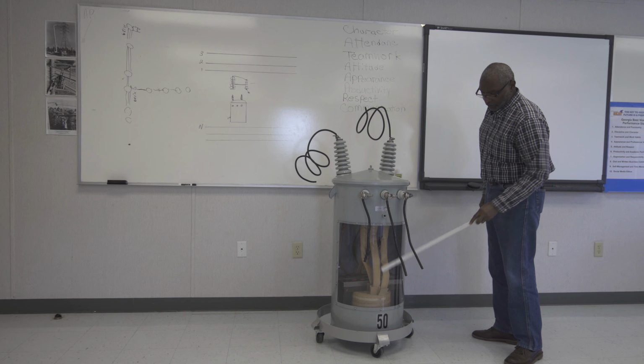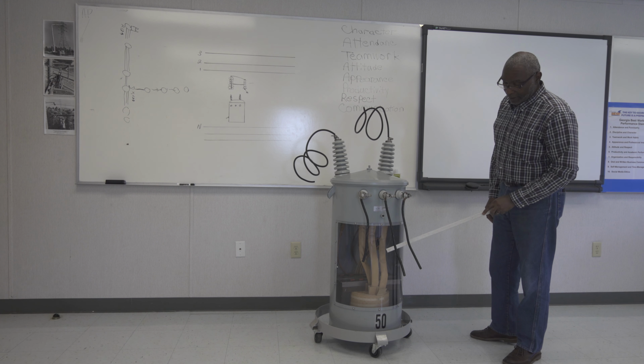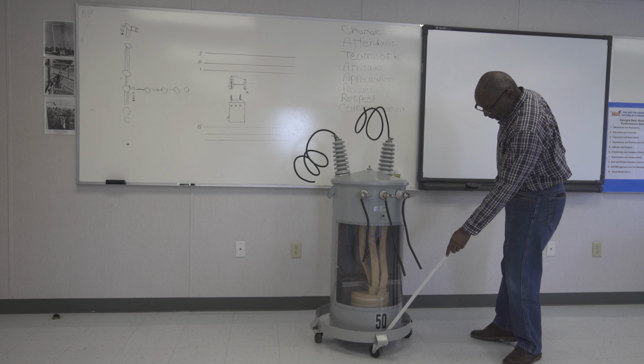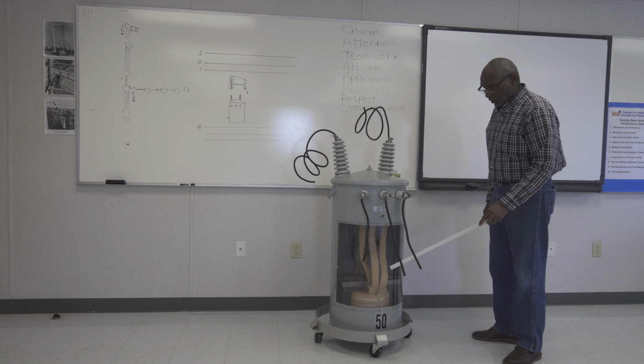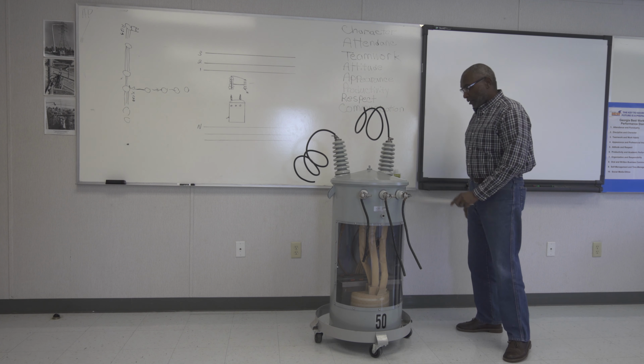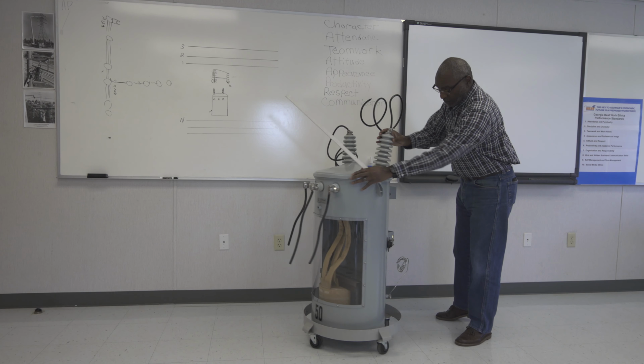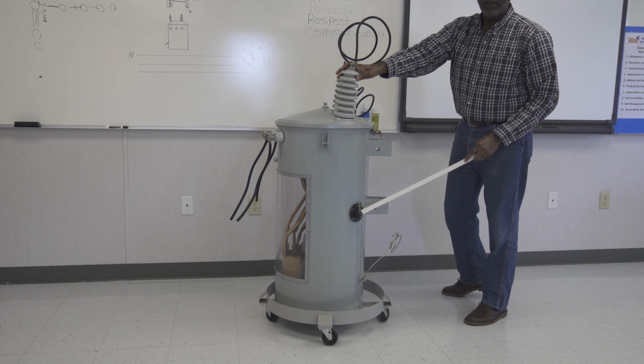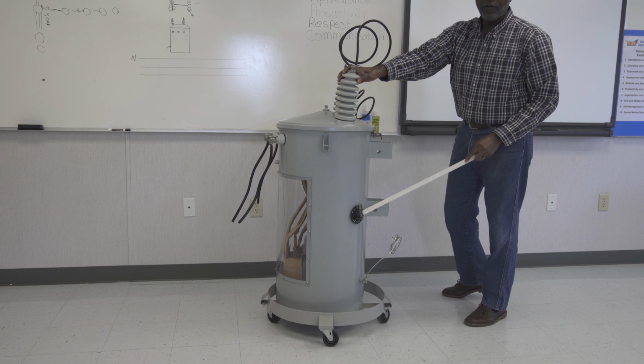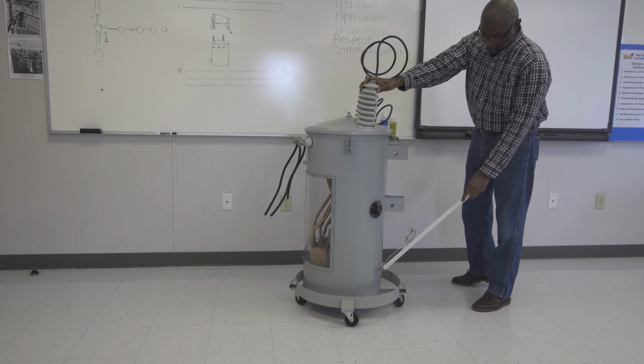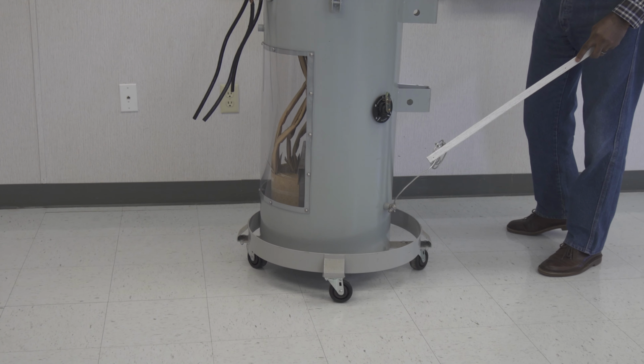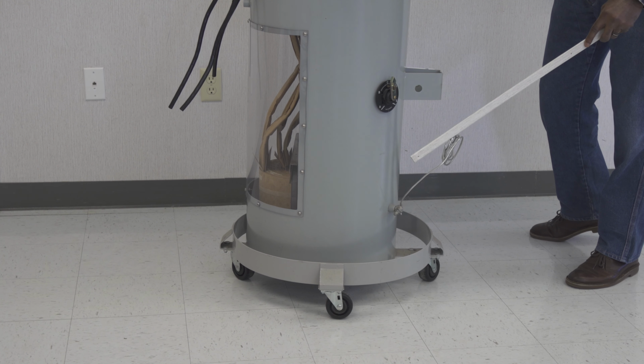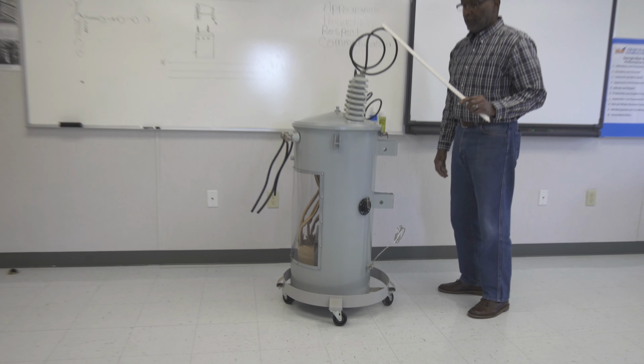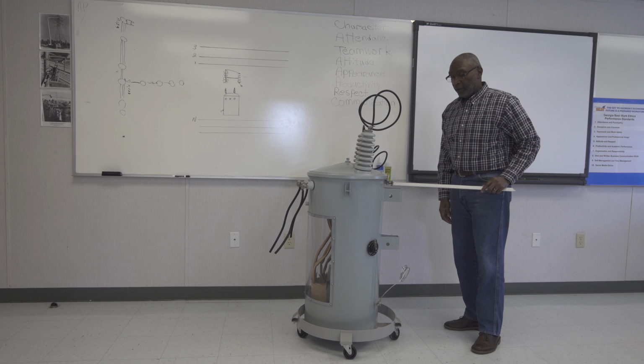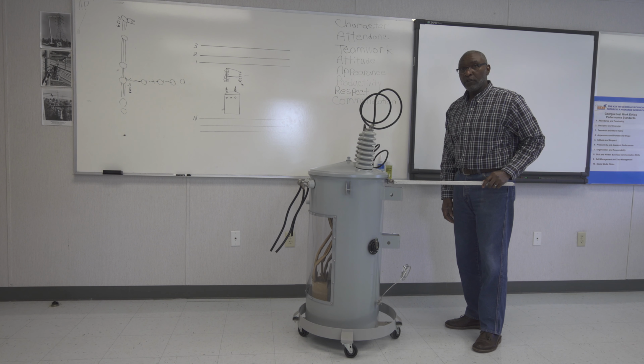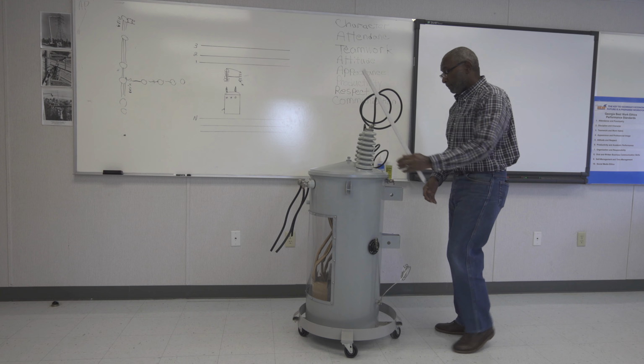kVA size of the transformer, remember it's going to be typically located right in this area, along with the blue sticker indicating non-PCB. On the back side, tap change from your system voltage from 7,200 to 14.4. Pot ground, which will hook up to your pole ground coming off the pole. Remember I said this would come down to your mainline neutral. You have here a bleeder, tank bleeder to bleed the pressure off from the buildup.